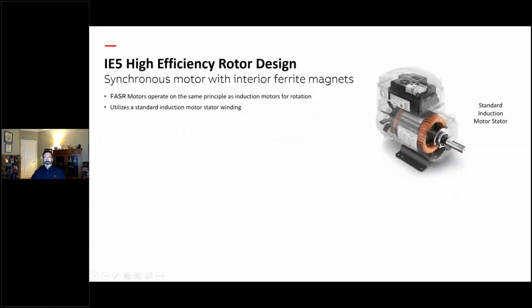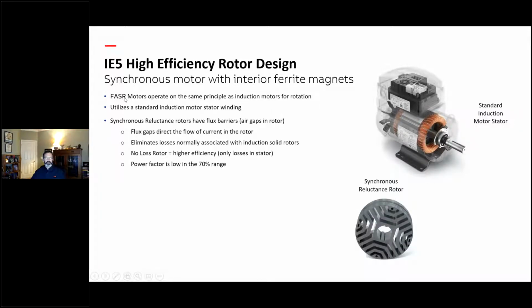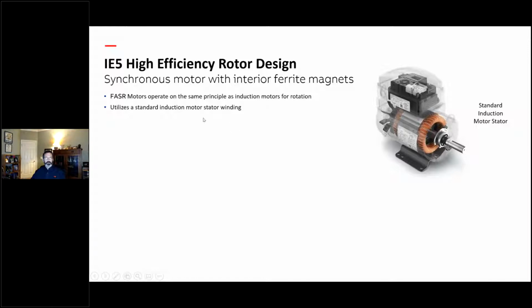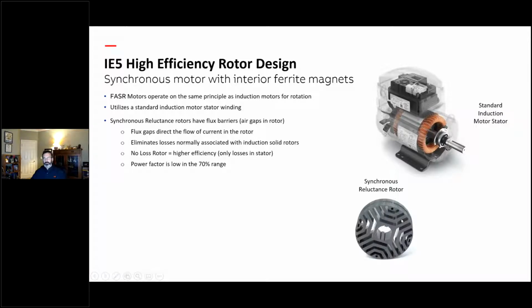I've kind of covered some of this again that I already talked about. FASR stands for ferrite assisted synchronous reluctance rotor. I already talked about what a synchronous reluctance rotor is, but it basically operates on the same principle as an induction motor, because it has a standard induction motor stator. So it gets rotation the same way an induction motor does, and utilizes a standard induction motor winding. And then here is a synchronous reluctance rotor, and you can see it has air gaps here. What the air gaps do is they channel the magnetic lines of flux through the conductive path. And so you get nice, clean magnetic lines of flux instead of getting circulating currents in a solid core rotor. And that basically eliminates the losses in the rotor.